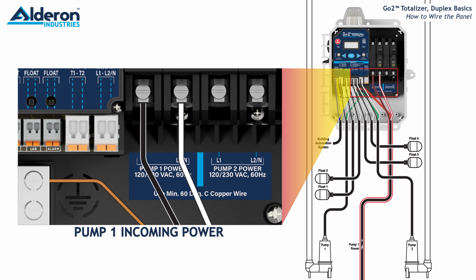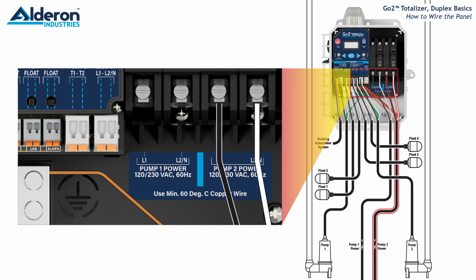Install the L1 and the L2 or neutral for the pump 1 incoming power circuit to the bottom of circuit breaker 1, with the L1 attaching to the left terminal and the L2 or neutral attaching to the right terminal, and install the ground wire to the ground lug. Install the L1 and the L2 or neutral for the pump 2 incoming power circuit to the bottom of circuit breaker 2, with the L1 attaching to the left terminal and the L2 or neutral attaching to the right terminal, and install the ground wire to the ground lug.